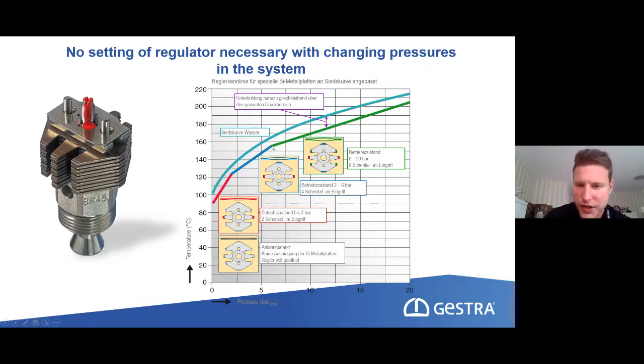And then for the rest of the saturated steam curve we have the linear characteristic, which is all fine because the saturated steam curve will also go into a linear characteristic. So this is how we manage to have such a curve also at lower pressures for the bimetallic steam trap.